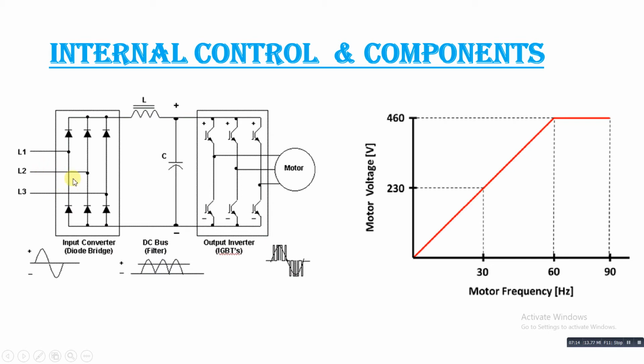Okay, so whatever the input AC, it will convert to DC. This DC bus will filter the DC, and it will feed to the output converter which is connected with the IGBTs. IGBT is nothing but insulated gate bipolar transistors. So this transistor converts DC to AC, and while converting you can control the frequency, current or voltage, whatever the way you are controlling your output source. So this is the basic common logic applied in VFD.